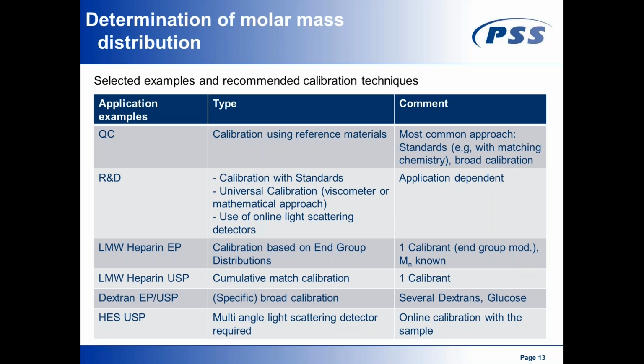For example, I can calibrate using polystyrene. I know the Mark-Houwink coefficients of that. I can analyze a polymethyl methacrylate. I also know the Mark-Houwink coefficients of that. And what I'll do is I transform my polystyrene calibration curve with a mathematical algorithm into a PMMA calibration curve, so that I can measure true molecular weights, for example, for my polymethyl methacrylate samples. This is a very different approach from the viscosity detector approach, because with a viscosity detector, of course, I can measure intrinsic viscosity and Mark-Houwink coefficients.